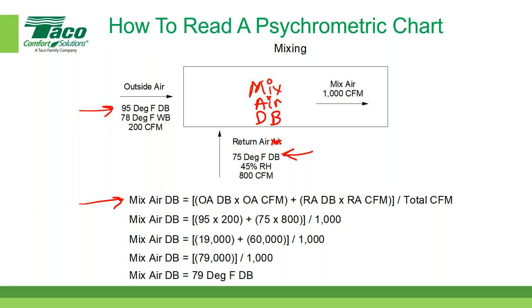So I've substituted the numbers. There's the 95 dry bulb outside, the 200 CFM of outside air, the 75 degree dry bulb, the 800 CFM of return air, and divide that whole thing by the total airflow, which is 1,000 CFM. I did the calculation out here. That's 19,000 plus 60,000, that sum divided by 1,000. So that's 79,000 divided by 1,000. So the mix air temperature is going to come out to 79 degrees dry bulb.